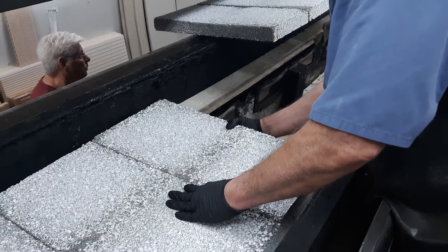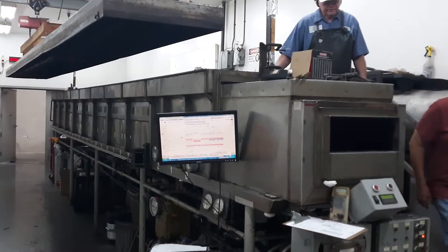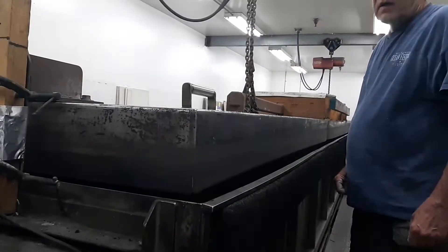Right now they're putting the EF block samples down. That's 24 foot long. At one end there's a four foot firebox. They put a four mile an hour wind in it and see how far it pushes the flame and how much smoke goes down there.